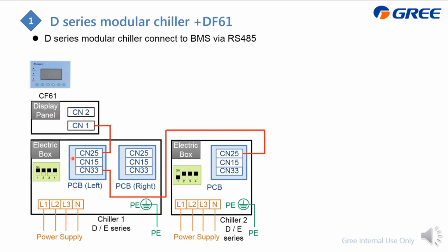Don't forget to change the dip switch to identify the different units. If this chiller connects to the controller, the dip switch setting should be like this.